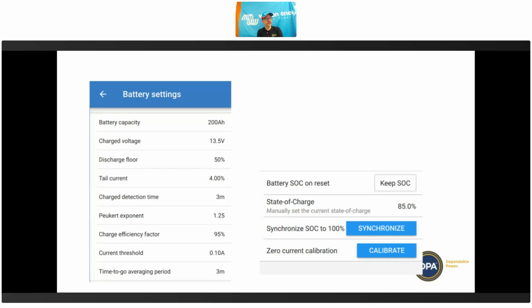And so different types of batteries, you're going to set that up differently. Sodium, you would set very, very low, like 5% perhaps. Lithium, you might set at 10 or 20%. And then a lead acid battery, you would set quite high, so tubular plate gel batteries in old off-grid systems, you would usually be cycling it down to 30%. So you might set the discharge floor as high as 60% perhaps. So that's a really important value as well. The rest of these values are less important, but it is good to understand what they are.